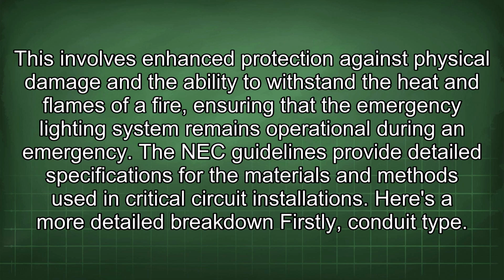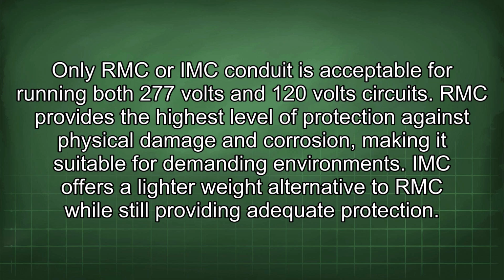Here's a more detailed breakdown. Firstly, conduit type. Only RMC or IMC conduit is acceptable for running both 277 volt and 120 volt circuits. RMC provides the highest level of protection against physical damage and corrosion, making it suitable for demanding environments. IMC offers a lighter weight alternative to RMC while still providing adequate protection.